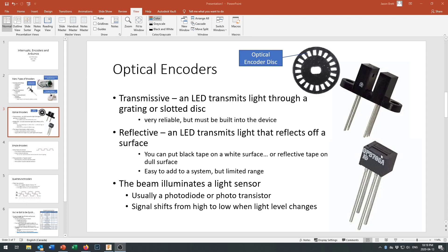You can also get a reflective setup, which is sometimes useful if you just want to figure out the RPM of a piece of equipment. For example, put a piece of black tape on a lathe chuck or drill chuck, put a reflective sensor nearby, and as the black tape comes around it stops the reflection off the shiny chuck and you see a change in light. The catch is that reflective sensors usually need to be held pretty close — within a couple of millimeters — unless you have a highly focused one, so you have to be precise. Not everything has to be magnetic or optical.